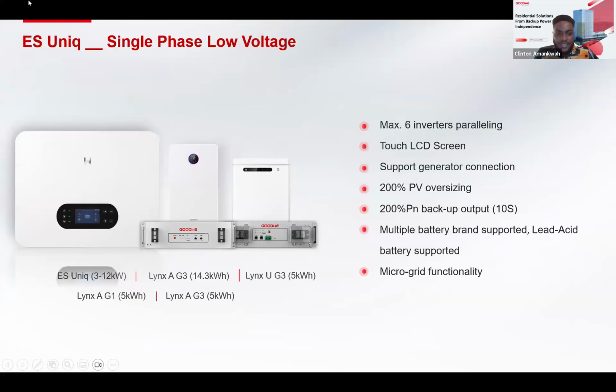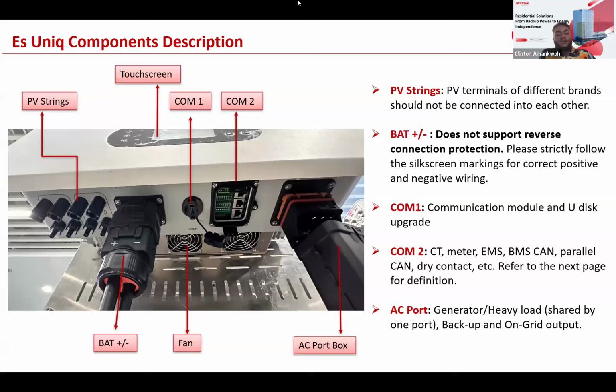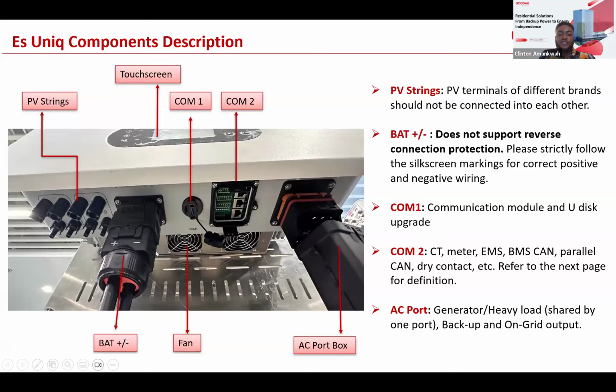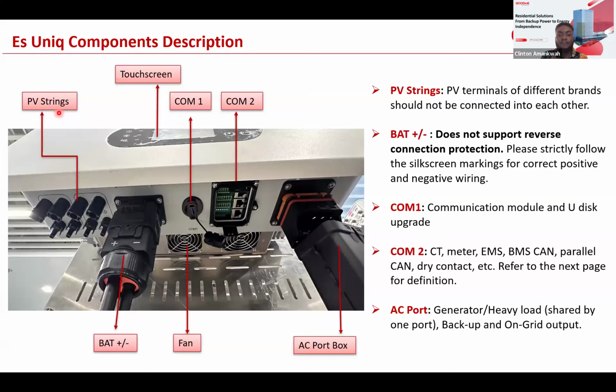All right, thank you so much. So maybe we can go to the next slide. All right. So this here is just to explain to you the component description of the ES Uniq inverter. So like I said, the ES Uniq is a single phase low voltage inverter that's compatible with both lithium and lead acid batteries. So what you see from the very far left where we have the PV string is the PV input slot, where you slot in your strings from your PV panels. It comes with a maximum of 2 MPPT. You can get 2 strings per MPPT. So you have 4 slots for your string input.